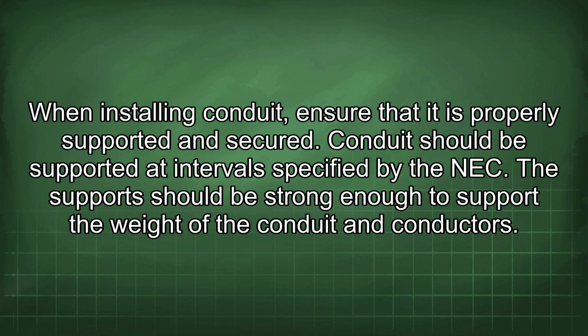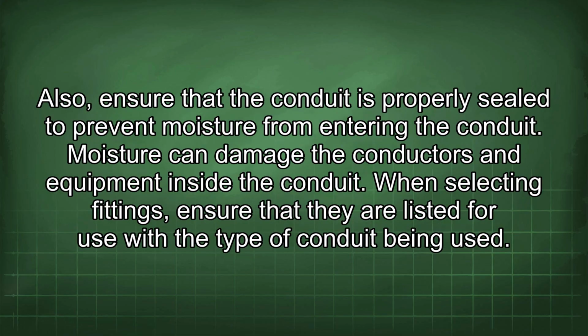When installing conduit, ensure that it is properly supported and secured. Conduit should be supported at intervals specified by the NEC. The support should be strong enough to support the weight of the conduit and conductors. Also, ensure that the conduit is properly sealed to prevent moisture from entering the conduit. Moisture can damage the conductors and equipment inside the conduit.